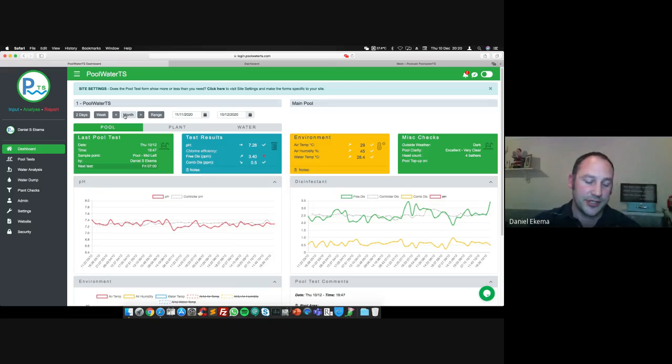Because of the guidance that came out with COVID from PWTAG, obviously trying to meet the 7 pH, we actually found that the chemical we had for our pH control, sulfuric acid, was affecting our alkalinity massively. Our alkalinity shot way down because we were trying to meet that 7. So that's why we have our pH a little bit higher, compensating with the chlorine being at a higher level.